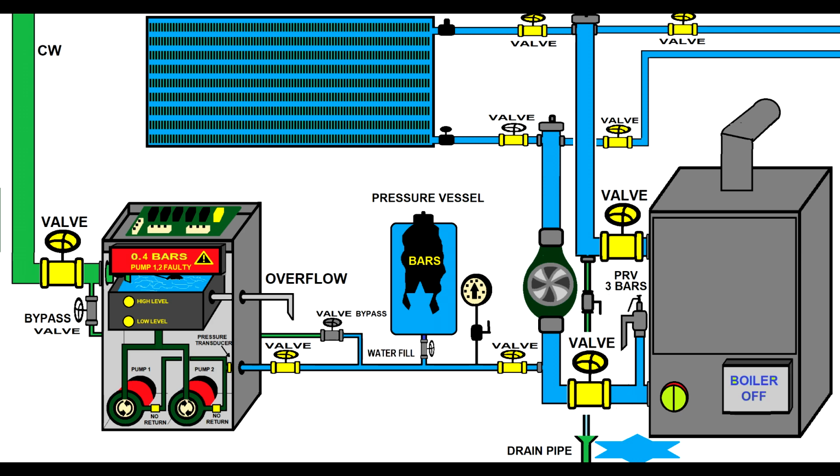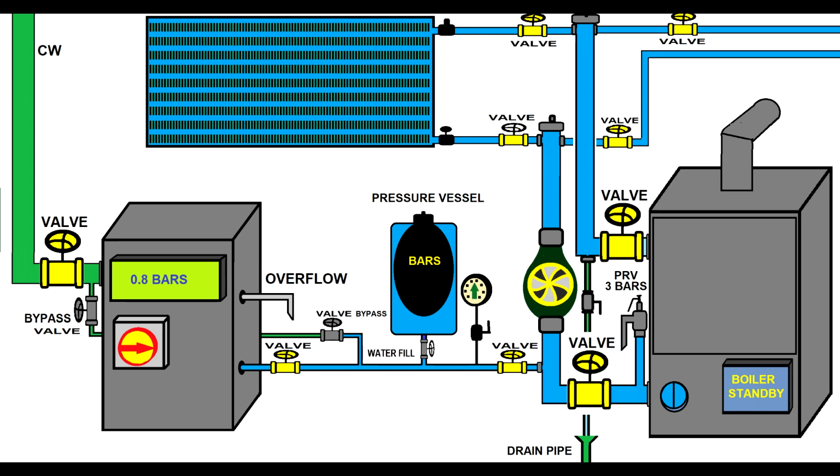If you have both pumps damaged, the pressurization unit obviously is not working. You will fill the system again just to satisfy your customer, and until you repair the pumps, technically you cannot do too much. But if you repair the pump without replacing or repairing the pressure vessel, then you will have a repeated fault, and that's not good either for the customer or for you.